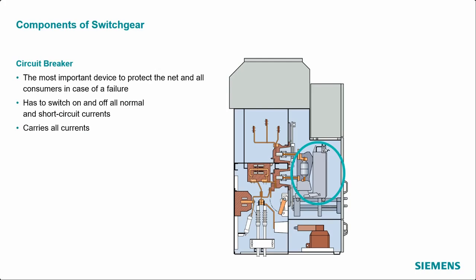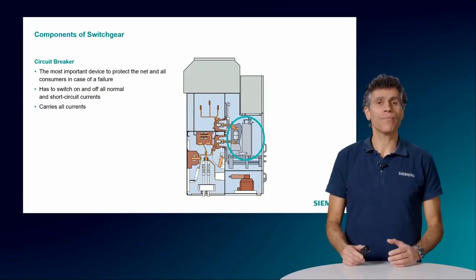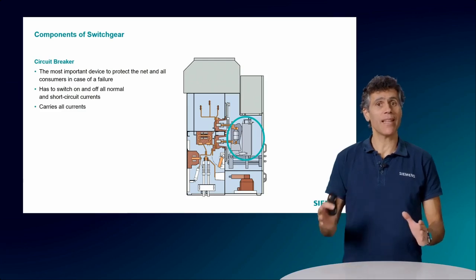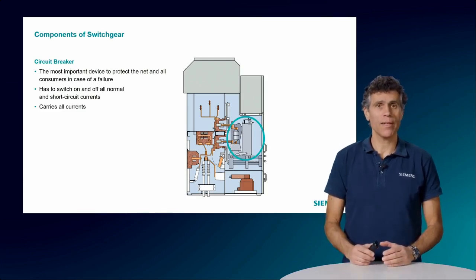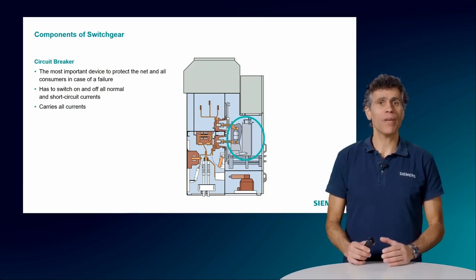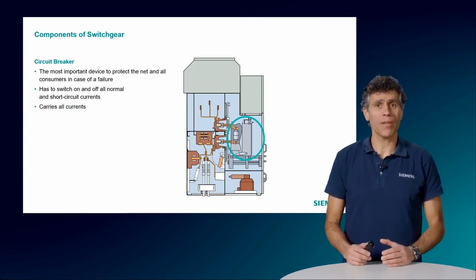since sometimes there are other components than a circuit breaker inside, as we will see later. It's also often called the module compartment room. The circuit breaker is the component that opens and closes the power, like the switch you will probably have somewhere in the room where you're sitting that turns the light on and off. But there is a very big difference between this breaker and the light switch you can see on the wall. Switching the light on and off is what is called operating under normal service.